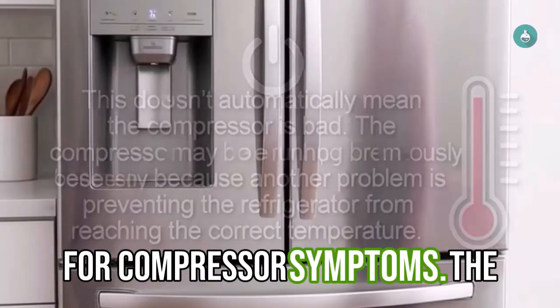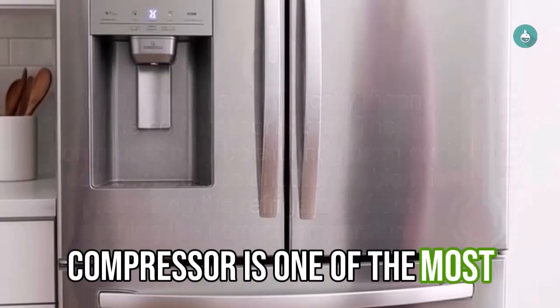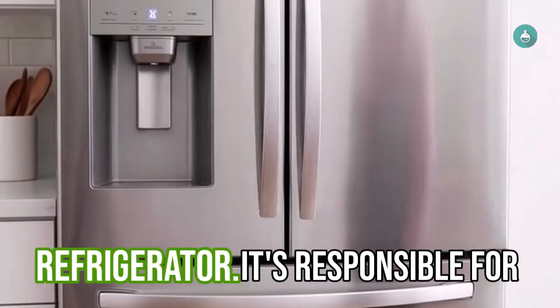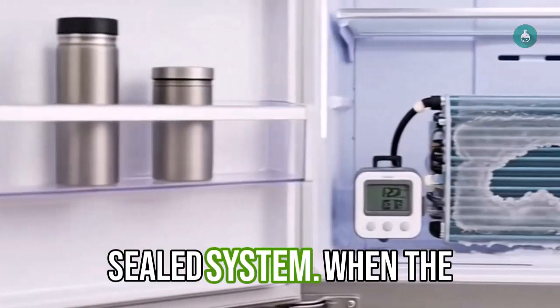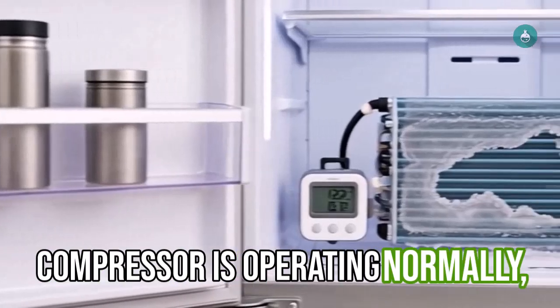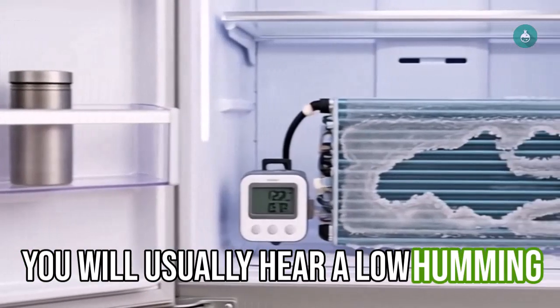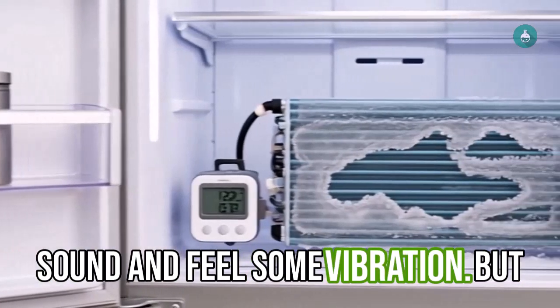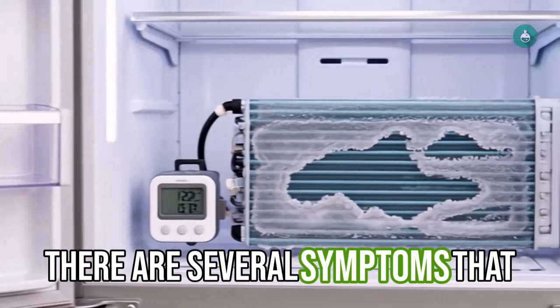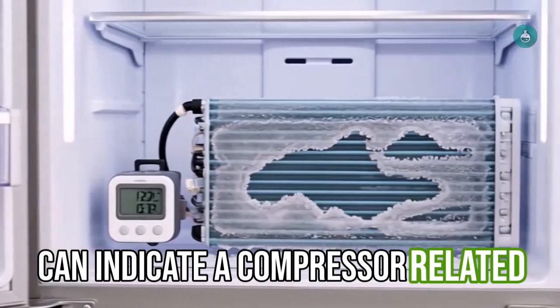Number 5, look for compressor symptoms. The compressor is one of the most important components in the refrigerator. It's responsible for circulating refrigerant through the sealed system. When the compressor is operating normally, you will usually hear a low humming sound and feel some vibration. But there are several symptoms that can indicate a compressor-related problem.